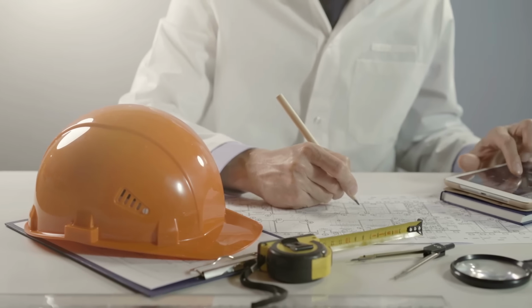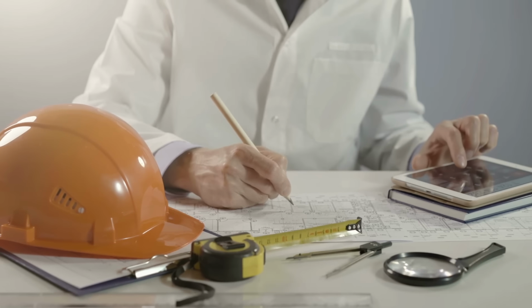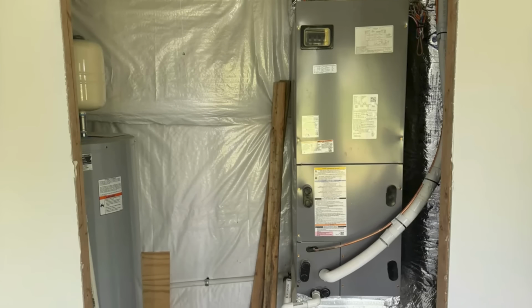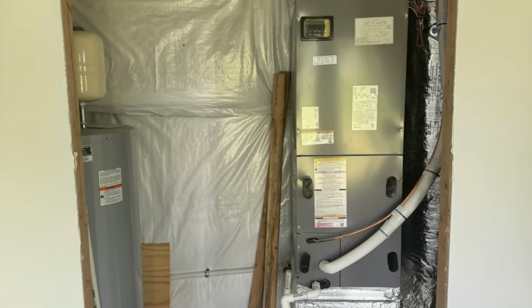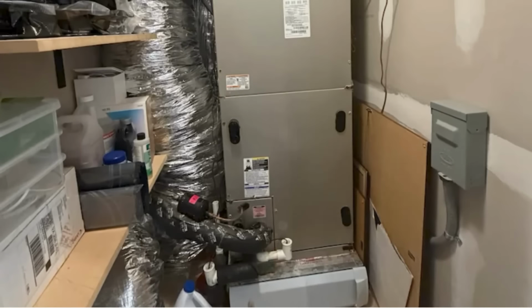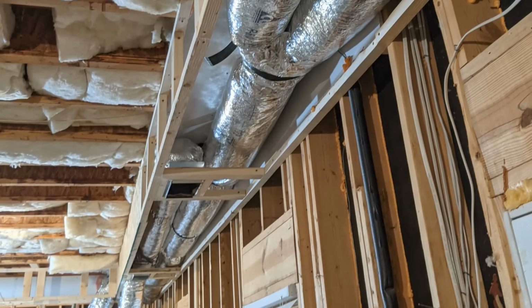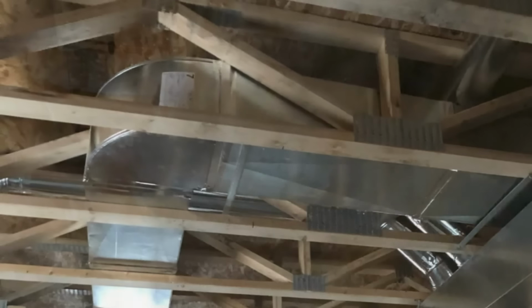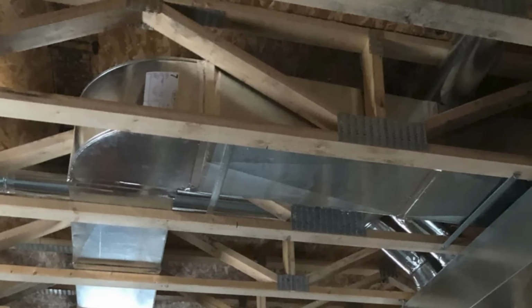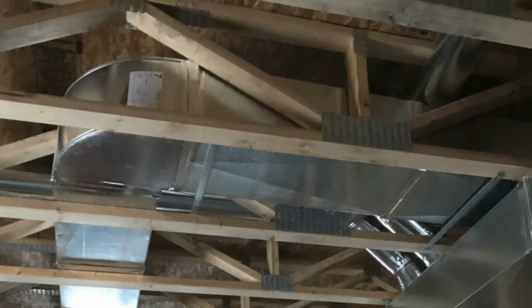Now, to pull this off, you need to be deliberate during the design phase. You need to plan for a dedicated mechanical closet inside the house to place your air handler. Don't treat mechanical space as an afterthought. For the horizontal duct runs, you can construct either a service soffit or a dropped ceiling below the ceiling's air barrier to keep the ductwork inside conditioned space.